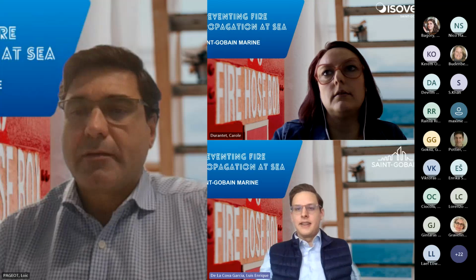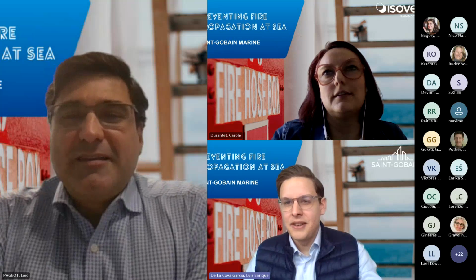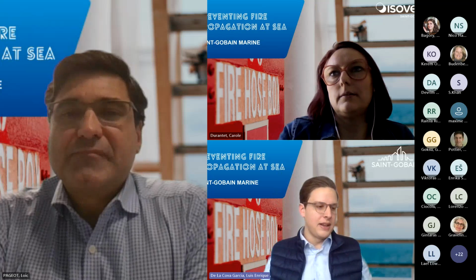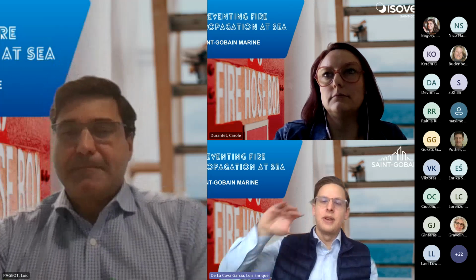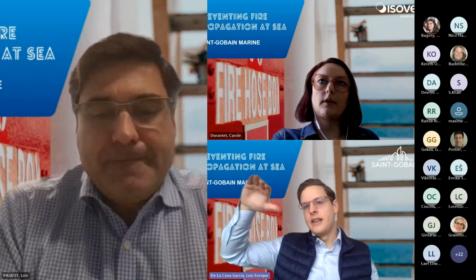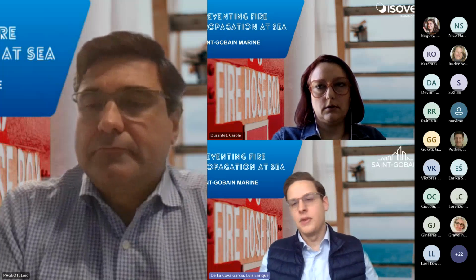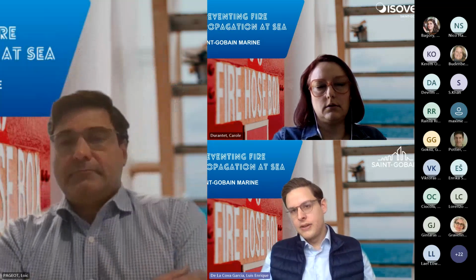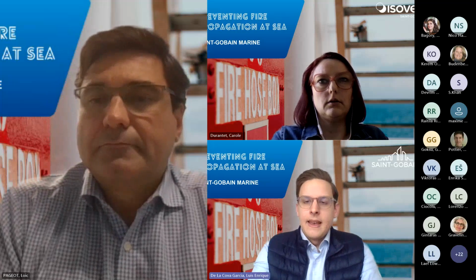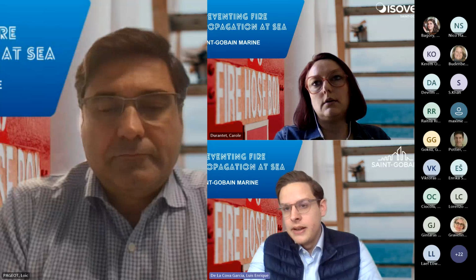I see that Hendrike is asking, what does H120 mean? Because I guess it was mentioned a couple of times during the webinar, but it was not on the graph. Briefly explained, the H stands for hydrocarbon rated solutions. What that means is that the testing procedure is done in a different way, where the temperature at the start is a lot higher, I believe around 900 degrees, and the curve maxes out pretty quickly. So the fire test itself is a lot more demanding. We see this used a lot in oil rigs, where there is a lot of fuel that would act as a combustion. So the requirements for the installed solutions are a lot more demanding.